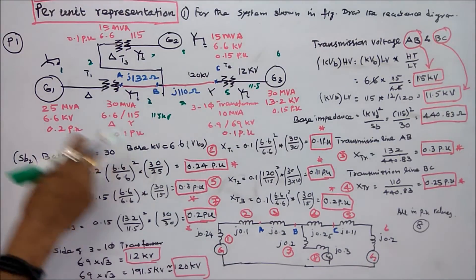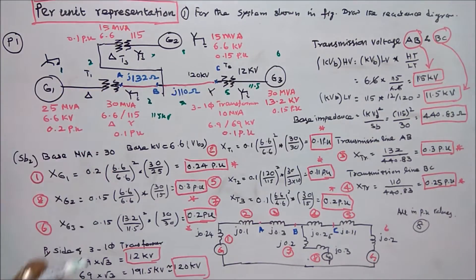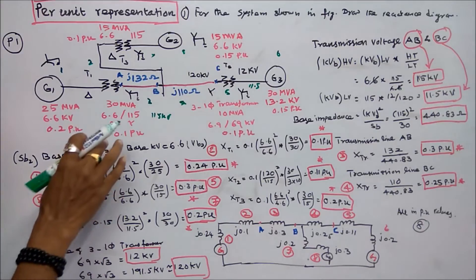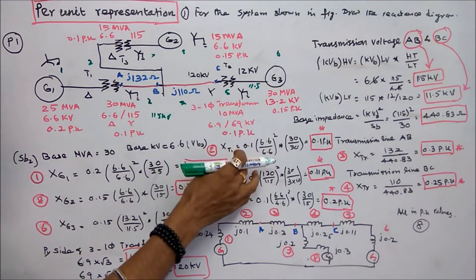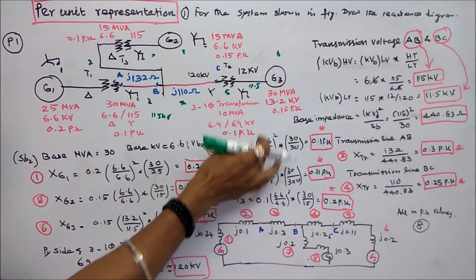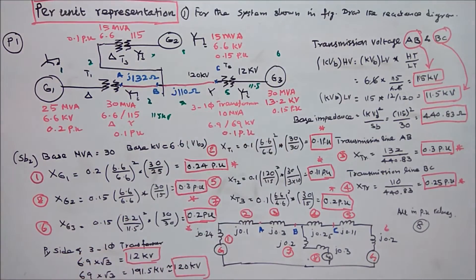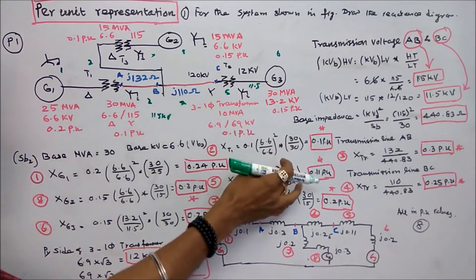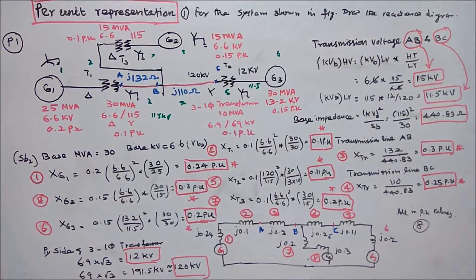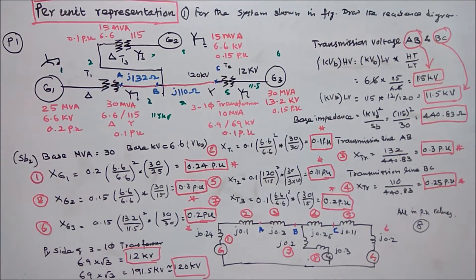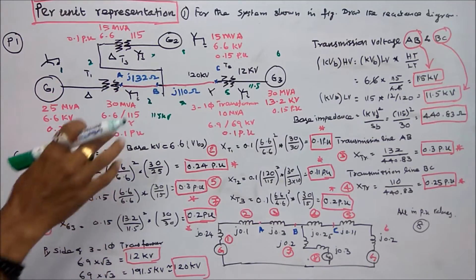The second component is transformer T1. The given reactance is 0.1. Per unit = 0.1 × (6.6/6.6)² × (30/30) = 0.1 per unit.